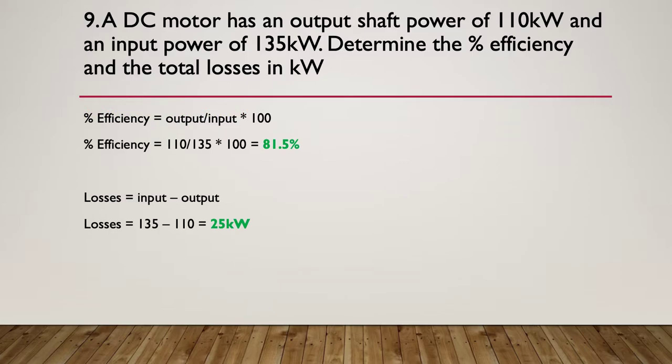So here's our calc. Our efficiency is simply going to be 110 divided by 135, so it's the numbers from the equation, output over input, and then simply multiply by 100 to turn it into a percentage. In this particular case giving us 81.5 percent.